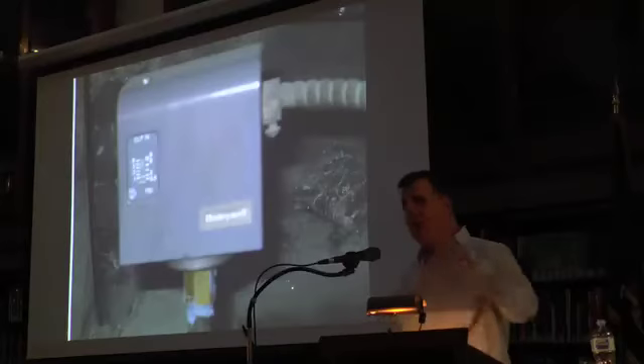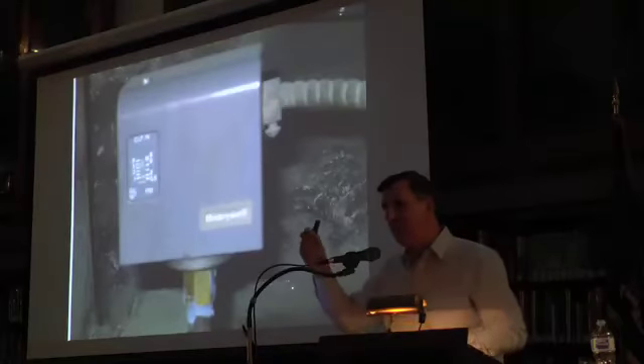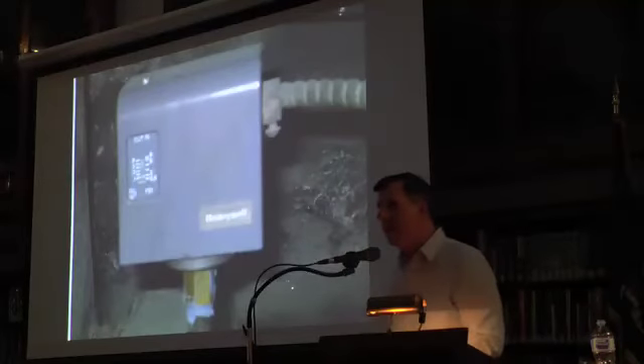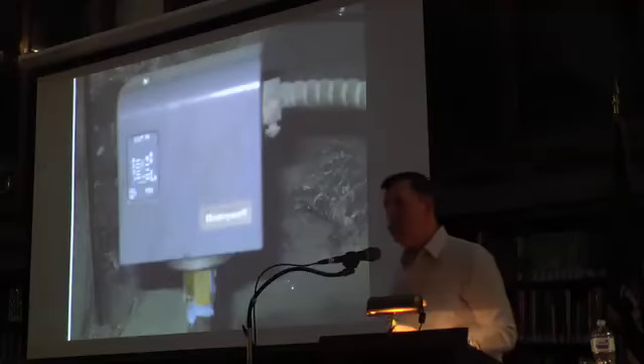I mean, it's got a cut-in setting on the outside, and then when you open it up, you'll see a wheel on the inside that says differential. So cut-in plus differential gives cut-out, and that creates this sine wave. So cut-in, cut-out, cut-in, cut-out. It's going to make the boiler run like that. I said, why does it do that? Why can't it just come on and run? He says, well, that's because that's the way it does.